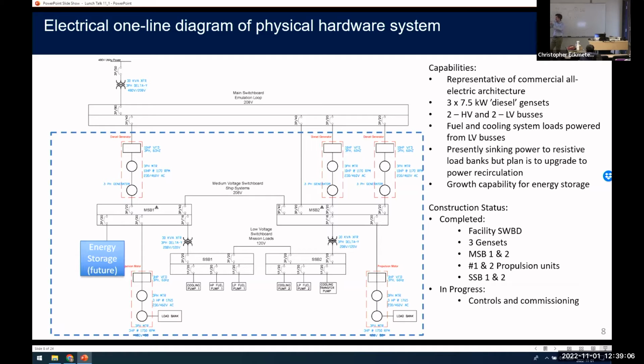So we take electrical power and run a control loop that emulates the dynamics of a diesel generator and allows us to inject faults. That makes mechanical energy like a diesel engine would, and that is coupled to a three-phase generator, which then makes three-phase power like you would see on a shipboard application. So as we load our shipboard buses, we'll see the same dynamics you would on a ship. When you load the generators, the frequency drops, so we get a normal droop curve, which you wouldn't get if you just plugged your system into a wall.